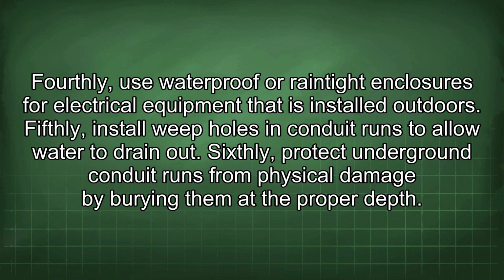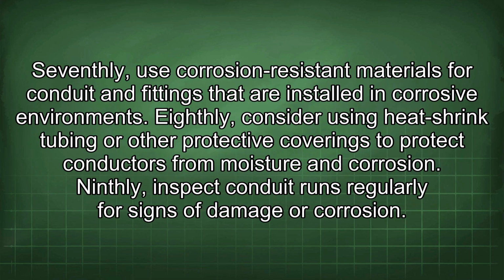Fifthly, install weep holes in conduit runs to allow water to drain out. Sixthly, protect underground conduit runs from physical damage by burying them at the proper depth. Seventhly, use corrosion-resistant materials for conduit and fittings that are installed in corrosive environments.